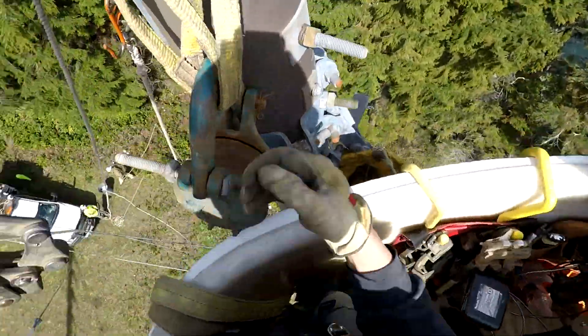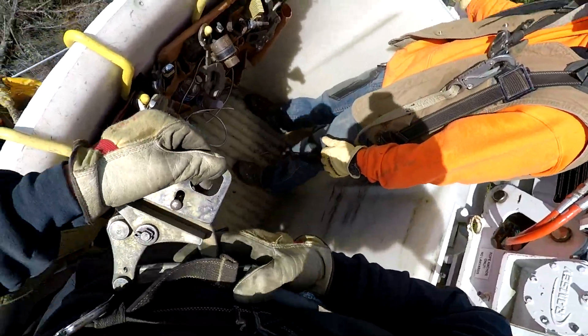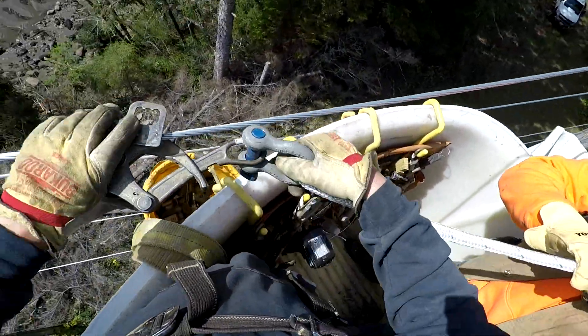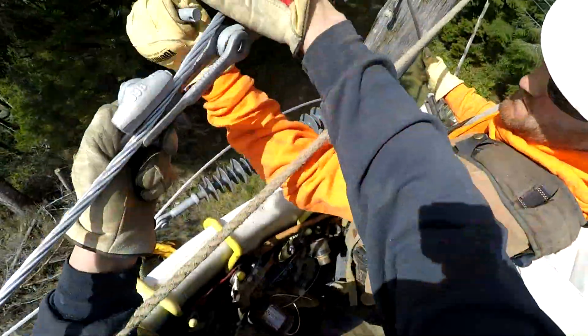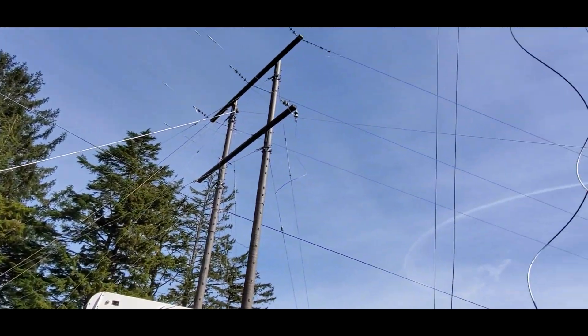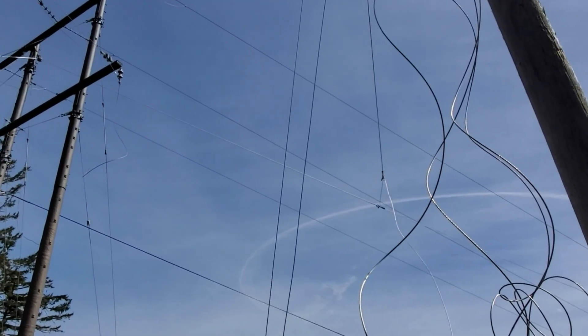This pulling rope is then threaded through the pulley. Crews then move the boom over and attach the pulling rope to the new conductor. The new conductor is then released from its temporary attachment. Tied off securely to a truck below, the truck then pulls the rope, which is attached to the conductor, swinging the conductor over to the structure for attachment.